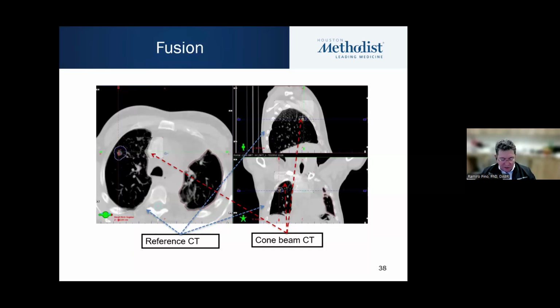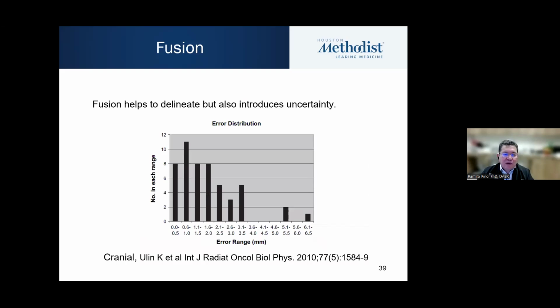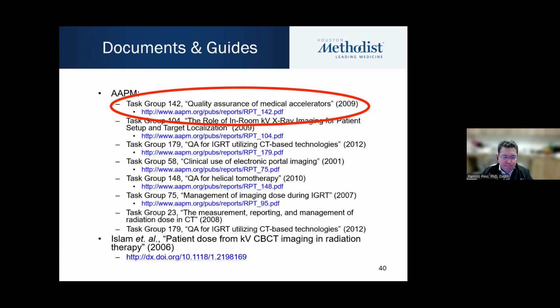One component I want to mention here very briefly is the fusion or co-registration, which is an important component because based on this co-registration is how we determine the shifts and how we apply them. Fusion or co-registration helps delineate targets and track targets for delivery, but it also introduces uncertainty. So it's important to know that co-registration is also a source of uncertainty. For treatment delivery image guidance, the main document we use is TG142, which is quality assurance for medical accelerators. It's already almost 15 years old, but it's very useful as well, with lots of details on what to do and often how to do it.